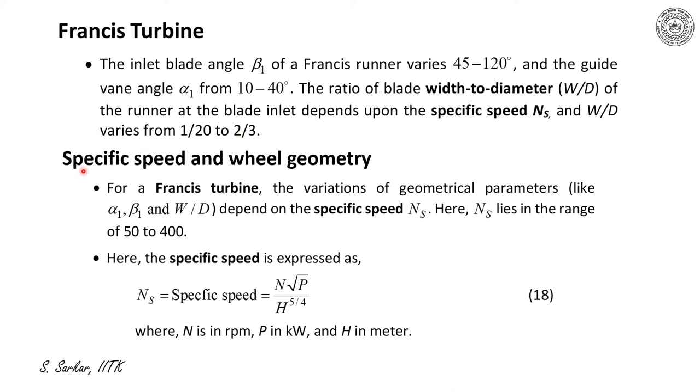So from this expression, one can appreciate there is a wide variation of beta 1 and W by D, and this depends on specific speed. Therefore, the specific speed and wheel geometry must be correlated, and this correlation I'll express now. So I have written in brief that for a Francis turbine, the variation of geometric parameters like alpha 1, beta 1, W by D depend on the specific speed Ns, where Ns lies in the range 50 to 400. And the specific speed here is expressed as Ns is equal to N root P over H to the power 5 by 4.